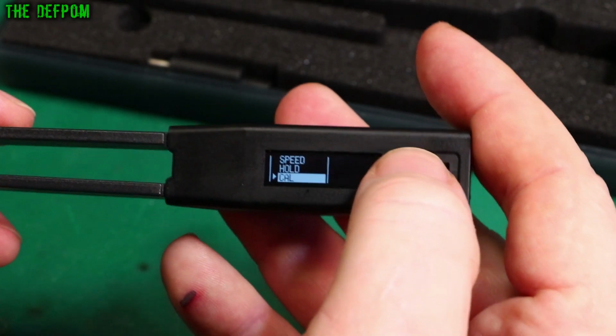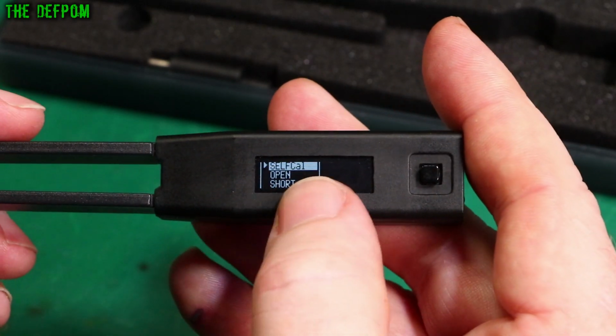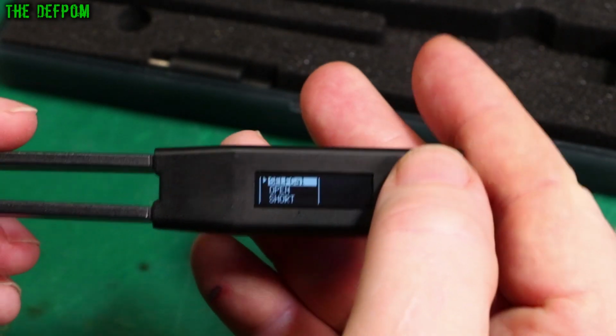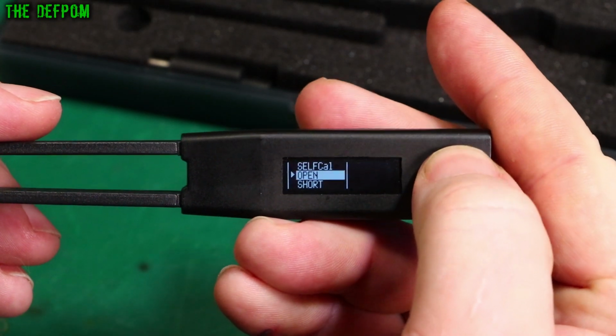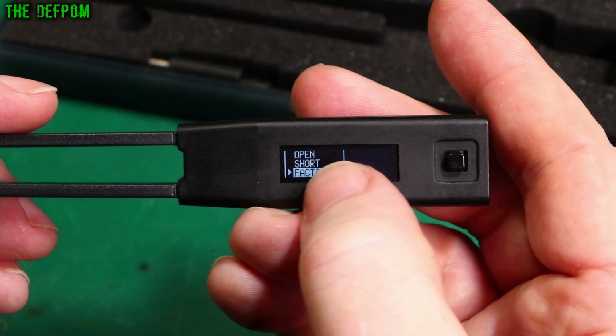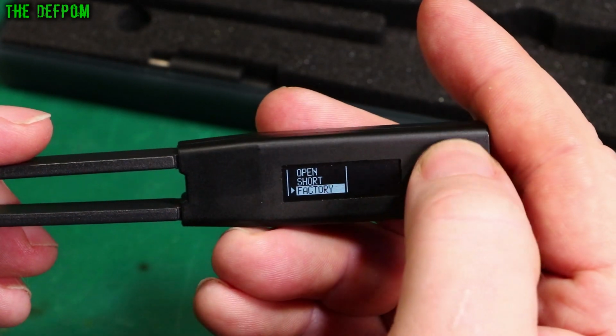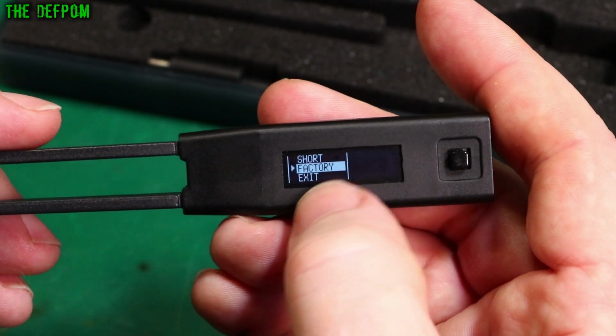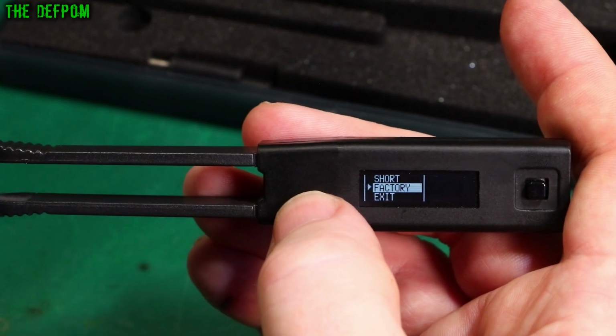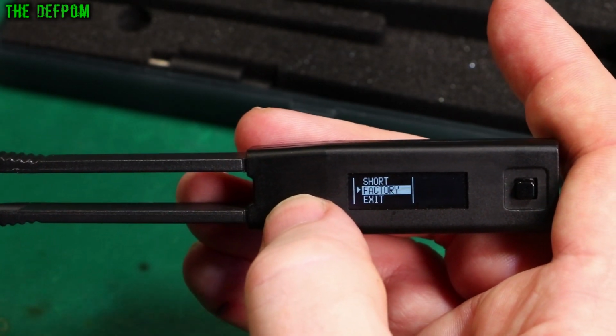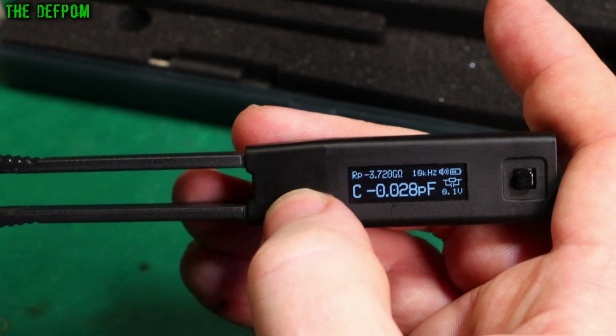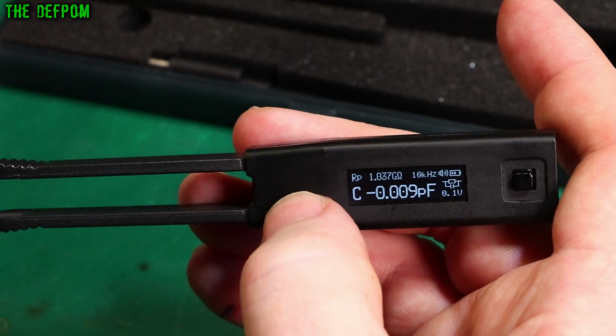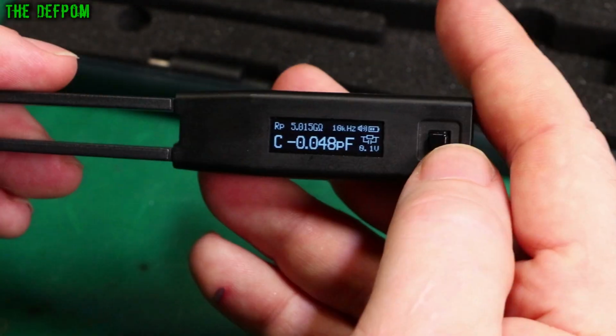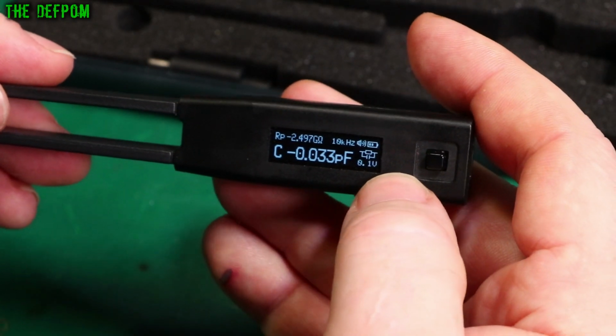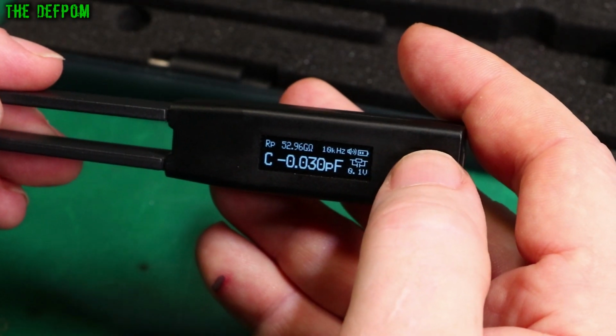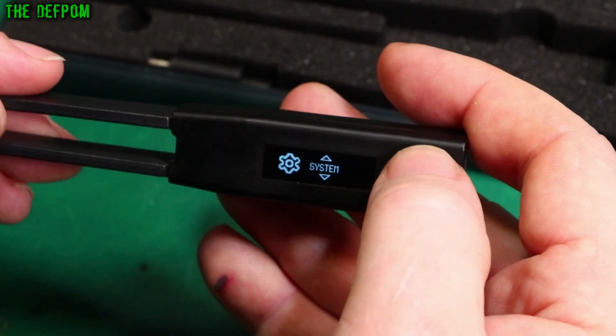So below hold we've got cal. So you've got self cal, open and short calibrations. Right, so you should do these periodically. And that's also part of the calibration board. There's also a factory calibration, which is, if you've got the right tools to do the job, you can do the factory cal. I don't recommend playing with that unless you actually have high precision references to use to do calibration on this thing. I don't actually know what it requires. Maybe Shannon can tell us. It'd be nice to actually know what it requires to do calibration. I don't want to go in and mess with it and find out I break it or mess up the calibration, not having the right things to do the job.